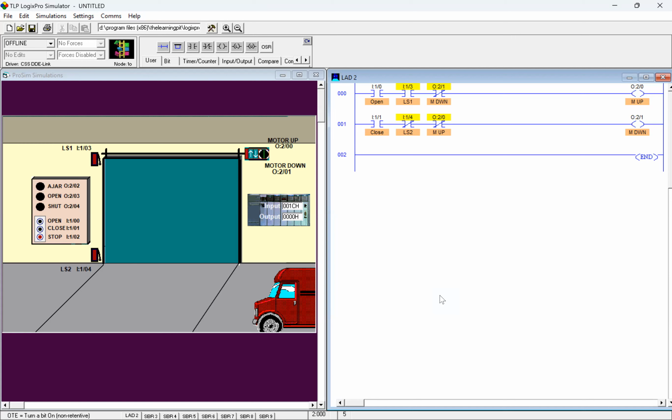Now, Tim, you're familiar with the forward reverse, right? What are you going to do on a forward reverse when you're out there? You're going to interlock the motors mechanically, right? Because you have that little device that goes between the two contactors. They both go to the same overload. So there's a mechanical device that locks one down so the other one cannot be on. If I hit one until I stop it, the other one will not go.